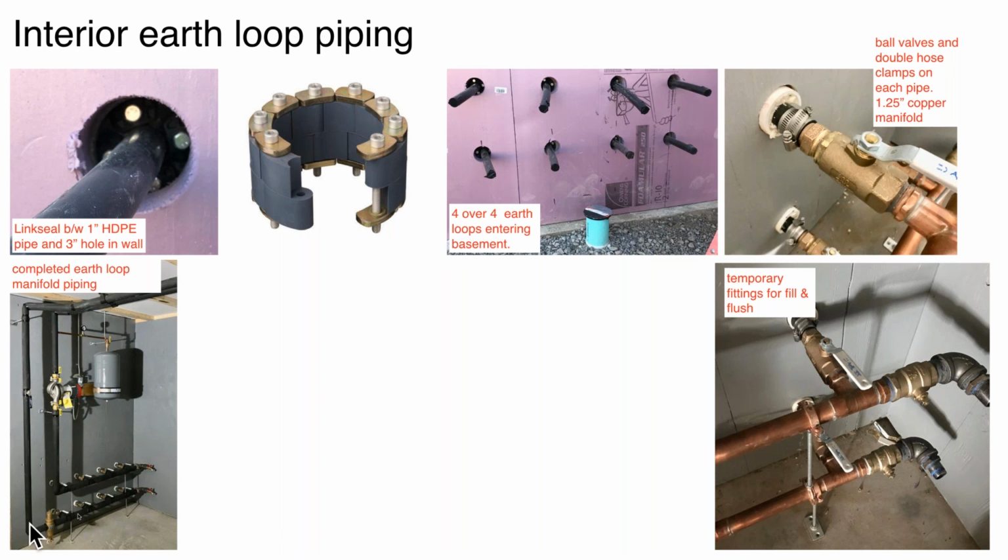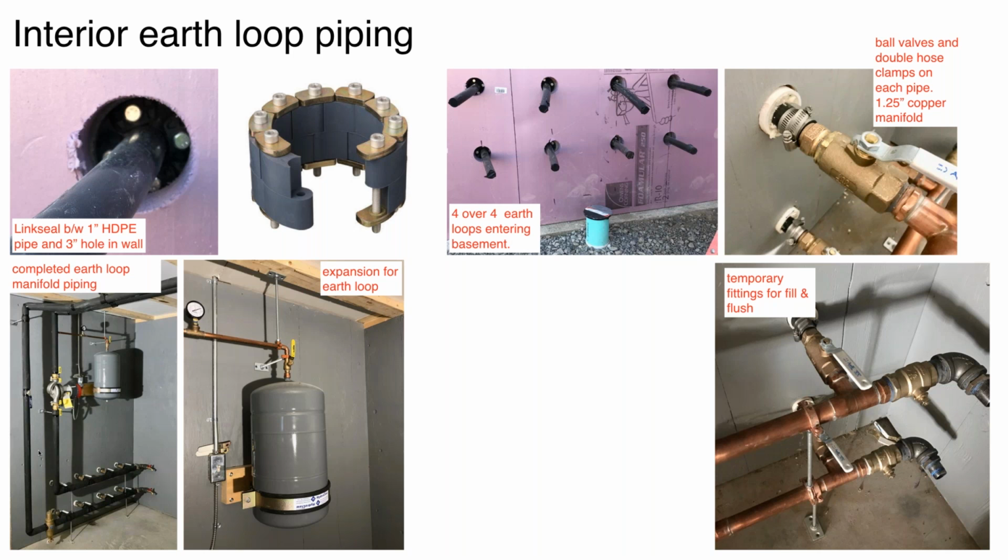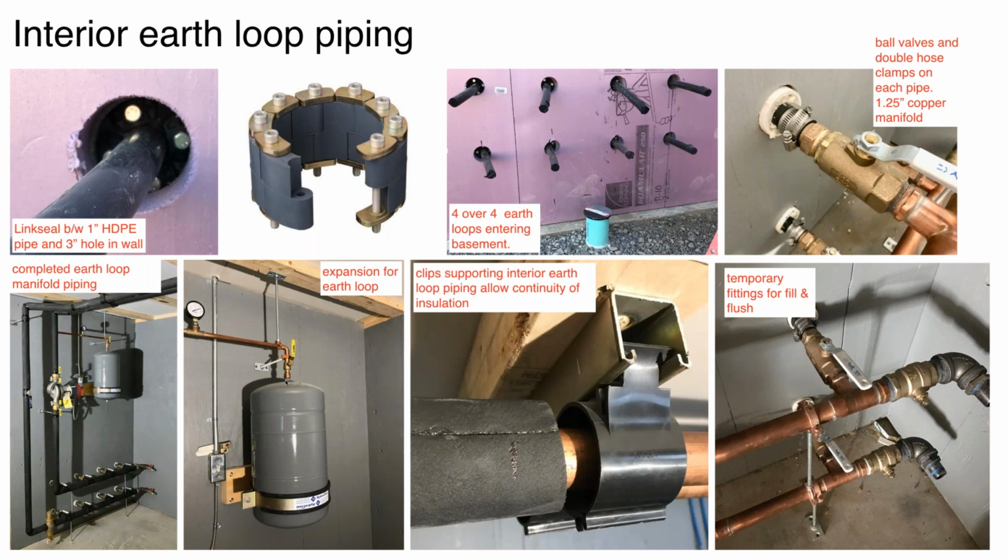And it is important to make sure that you get insulation on all this piping because that is going to run at temperatures that are well below the dew point of the interior air during the winter. And without the insulation, you're definitely going to get condensation. Okay. Just a close-up of the expansion tank. We use one of the Hydroclaw brackets here. And we also have a piece of 3/8 rod here holding that 1/2-inch tube, just so when somebody eventually bumps into this tank, they're not going to bend it up here at the neck.